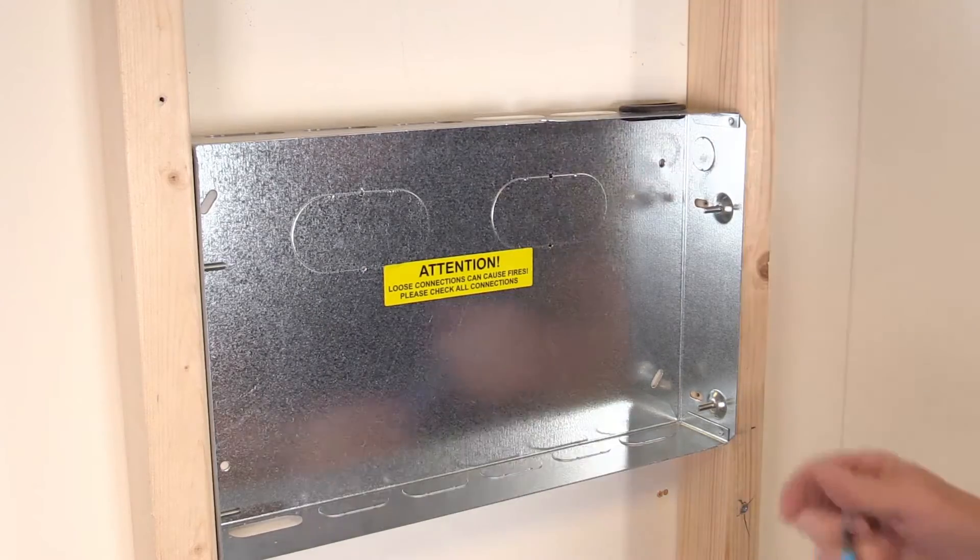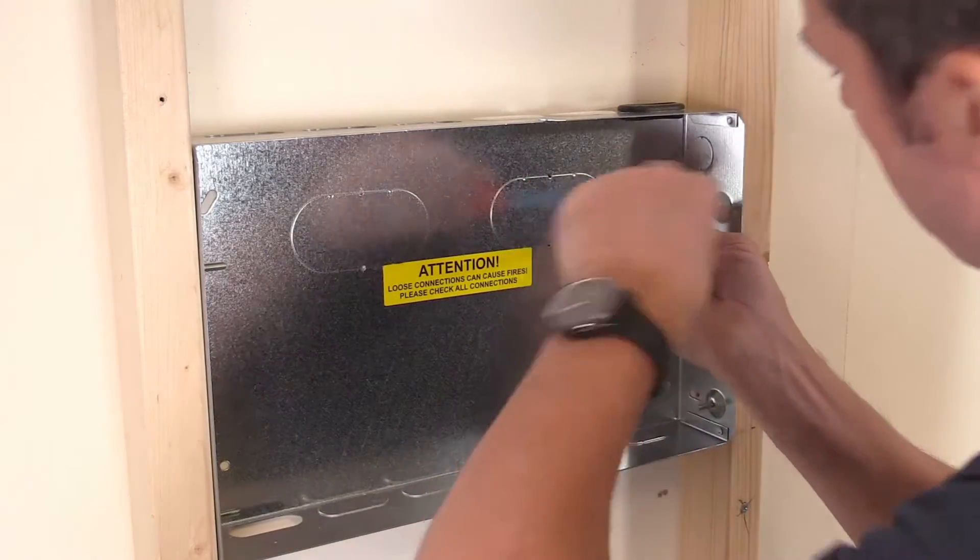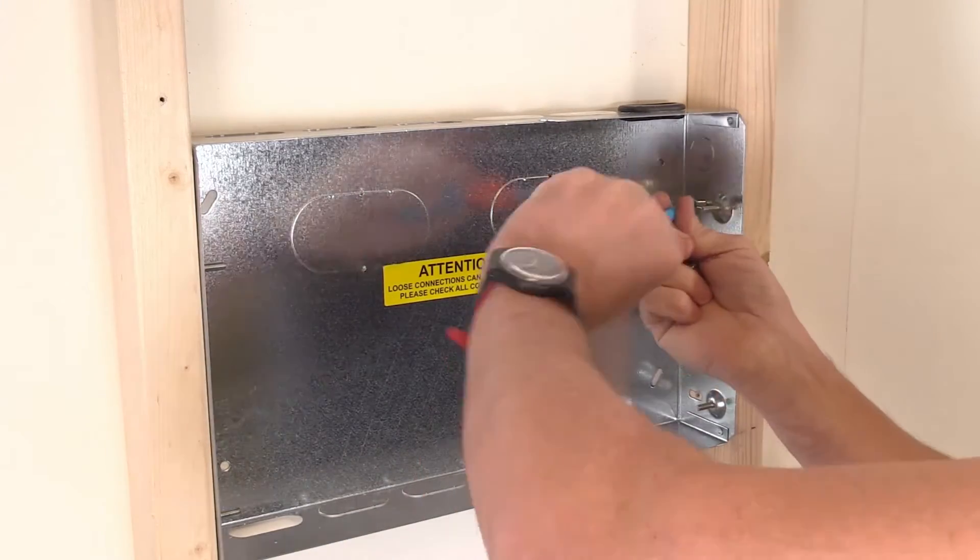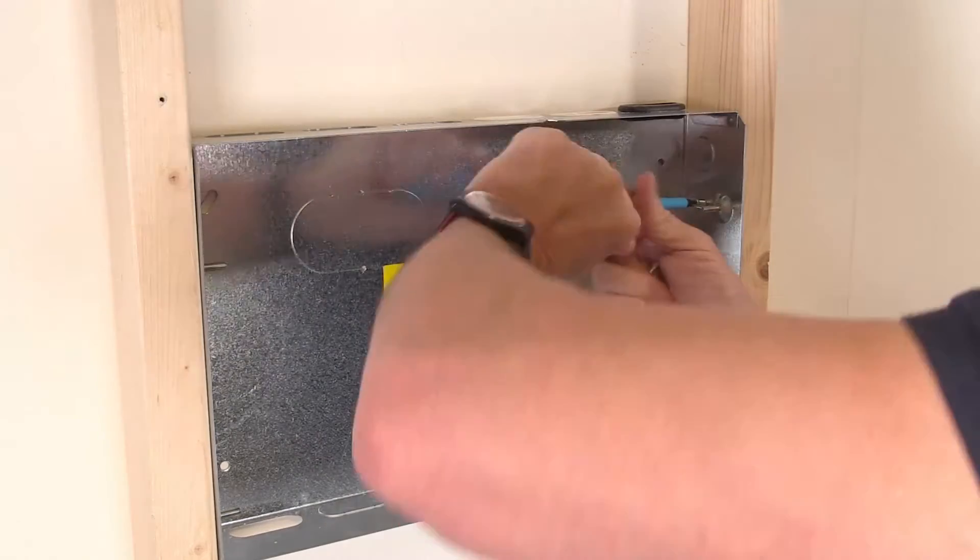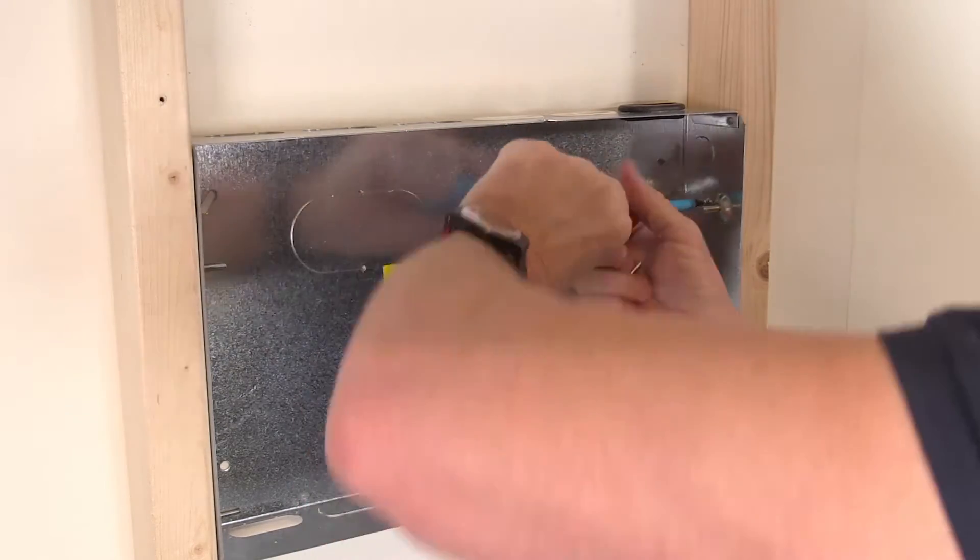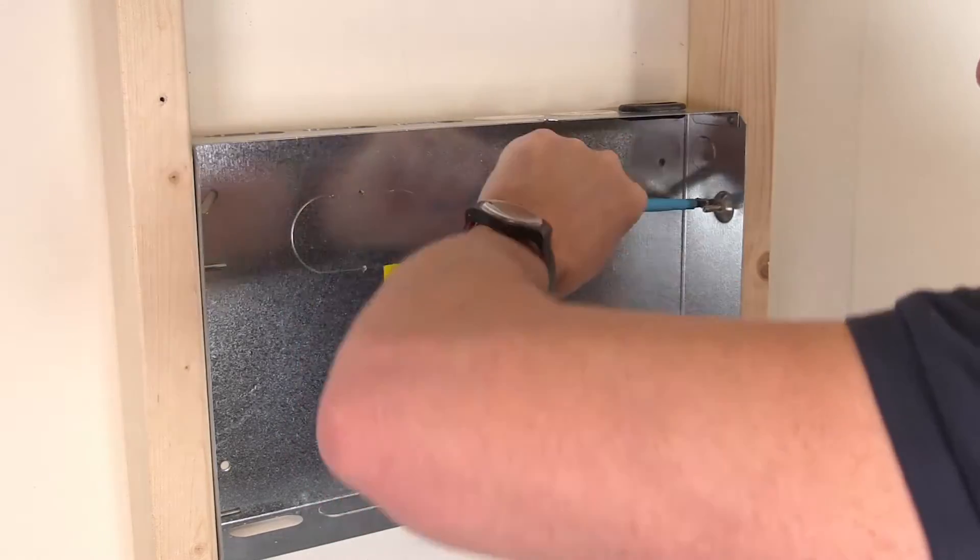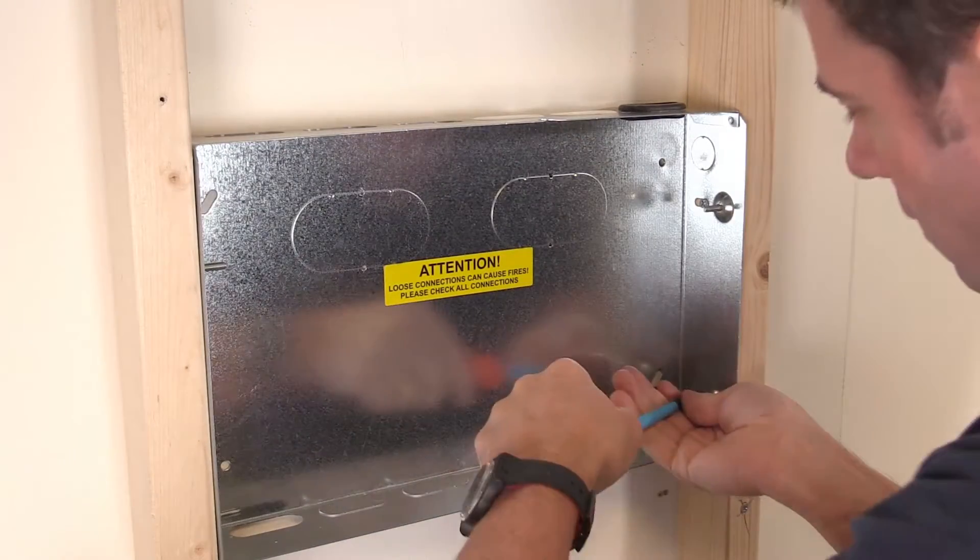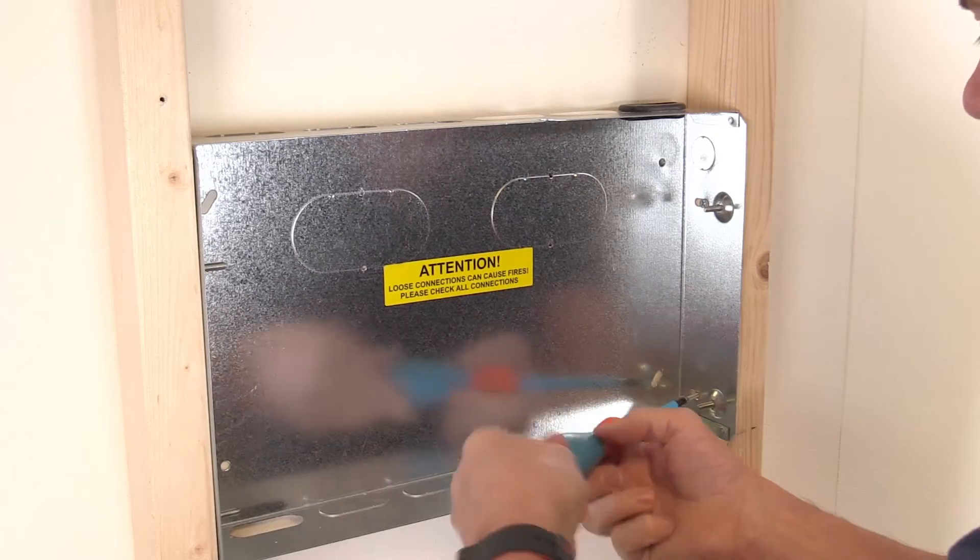Once you've got the height and depth right, use the slots on the inside edges to fix screws into the woodwork, securing the back box in place. It's worth checking at this point that the top and bottom edge don't protrude forwards of the stud work, as this will mean the board will be too far out of the wall when the cover is fitted.